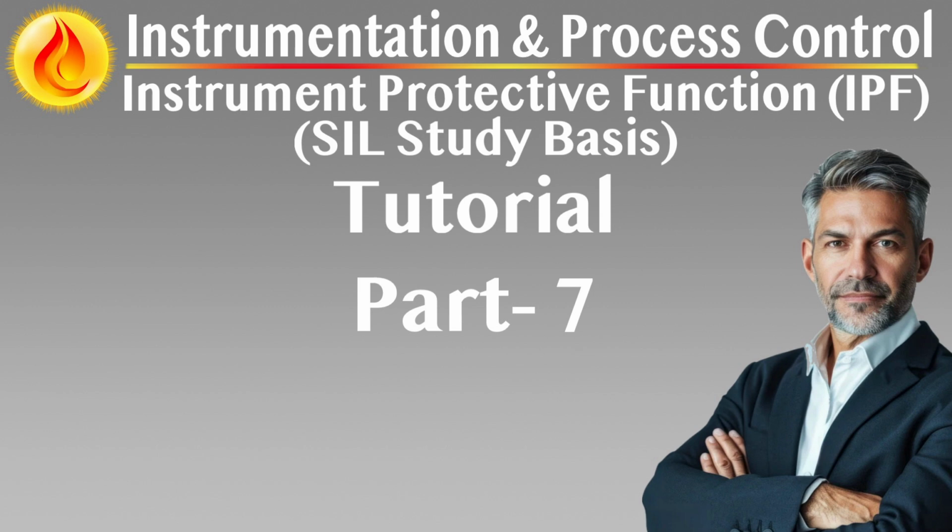Operational constraints and bypasses. Any required overrides or temporary disablement of the IPF during testing must follow strict procedures with compensating measures in place. Recording and use of test results. Document all test outcomes. Each test must be recorded with date, responsible person, results, pass-fail, and any failures or anomalies noted.